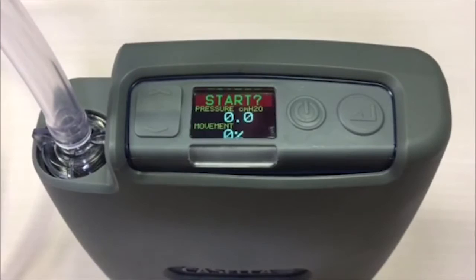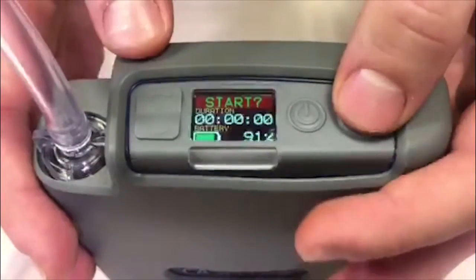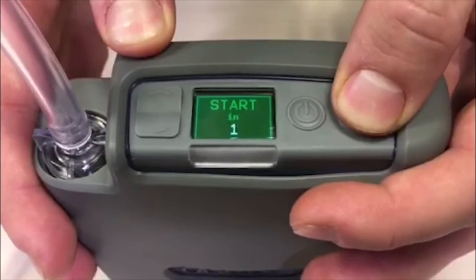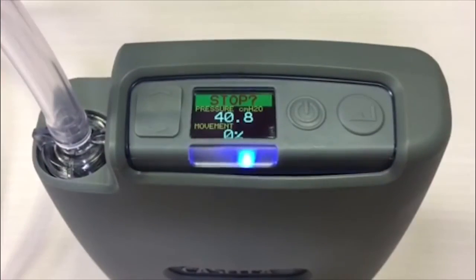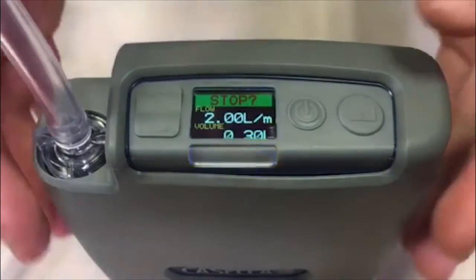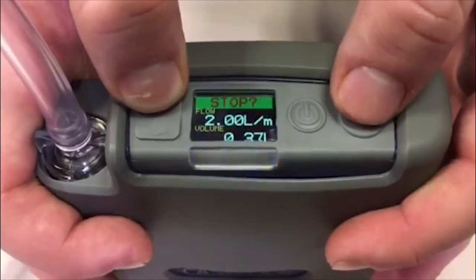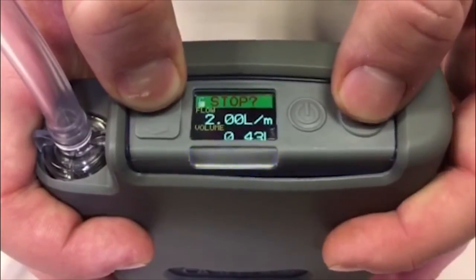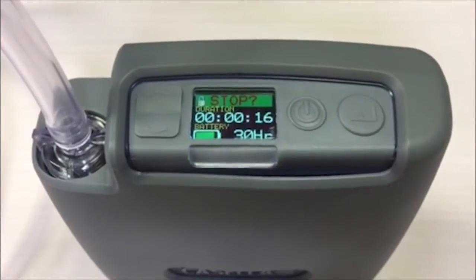Once the pump has been removed from the flow meter, hold the Enter key down to start the pump. It will then do a countdown of 3 seconds and the pump will start running. It is important to lock the pump to prevent tampering. To lock the pump, hold the up cursor down and tap the Enter key 6 times.